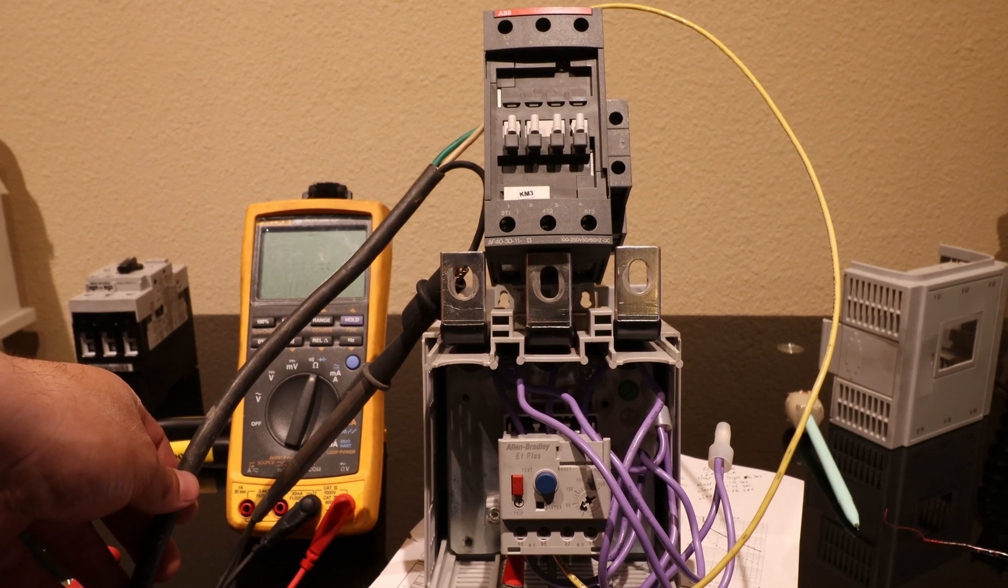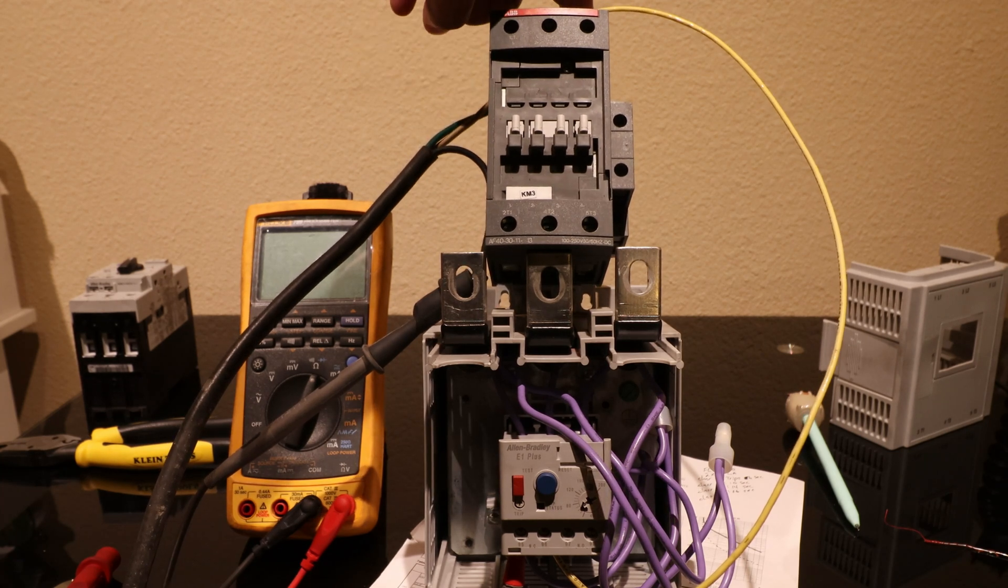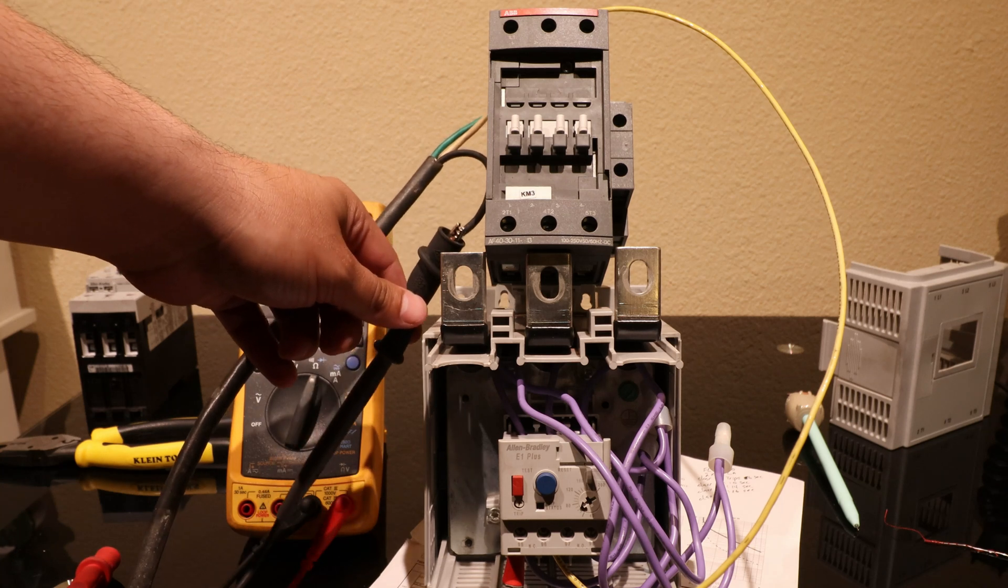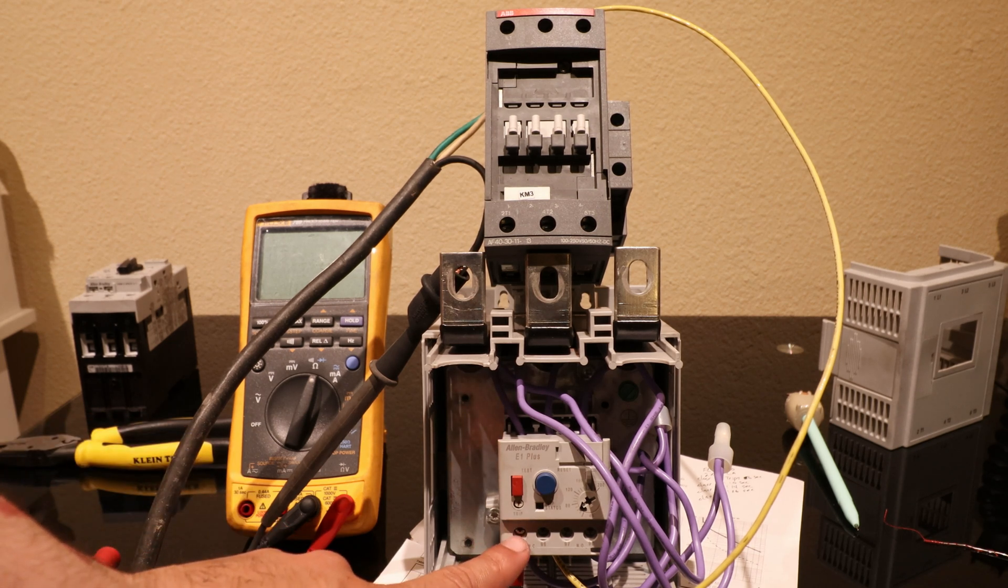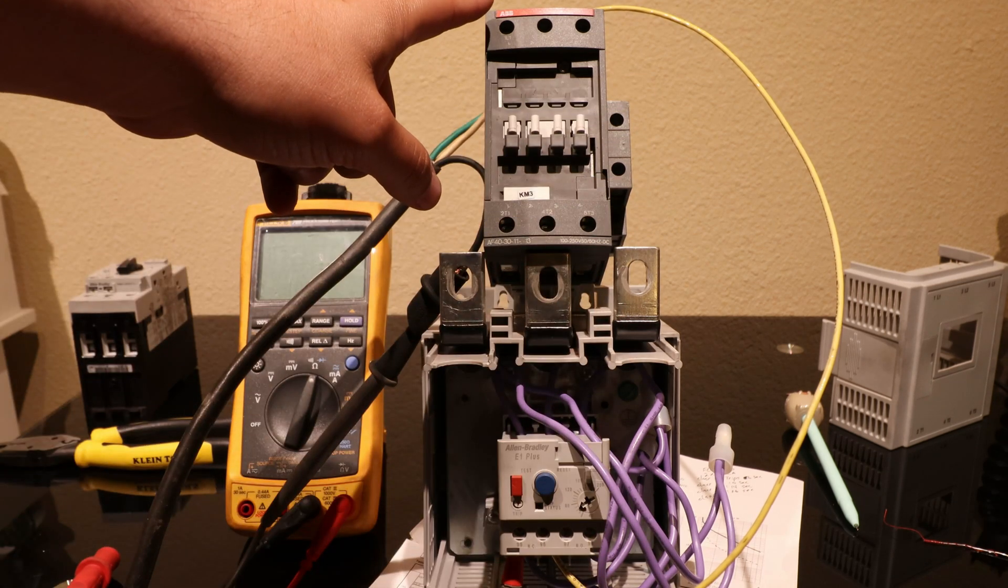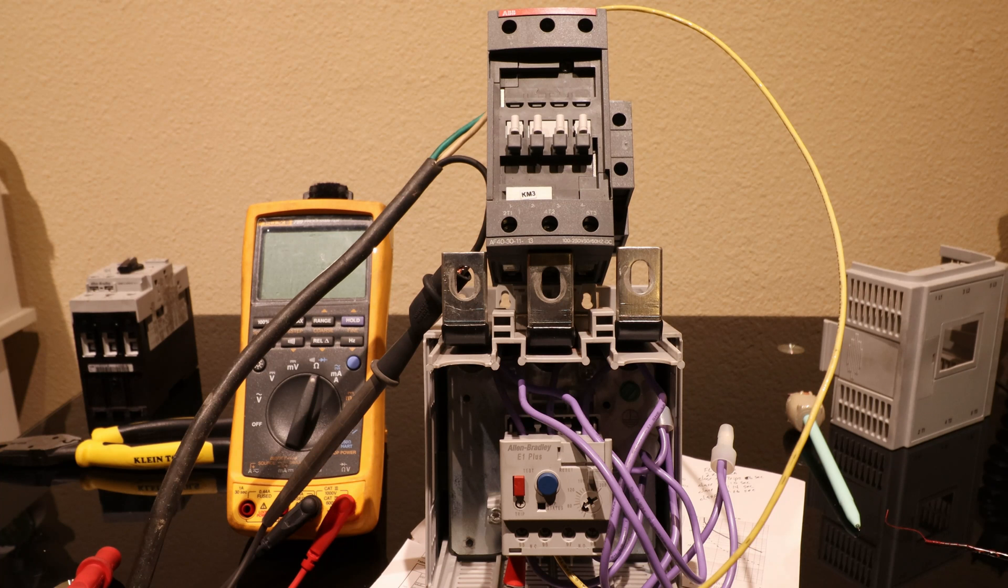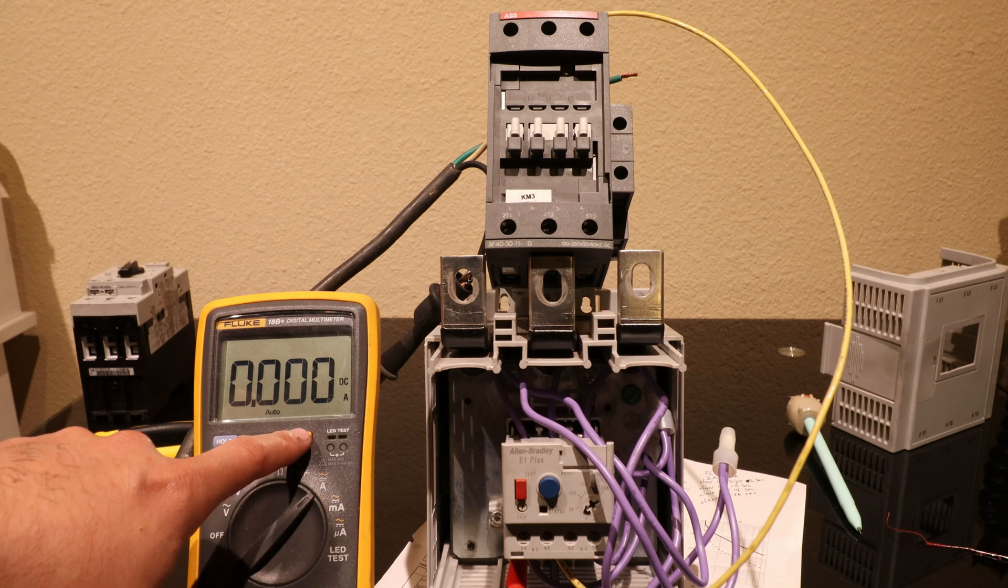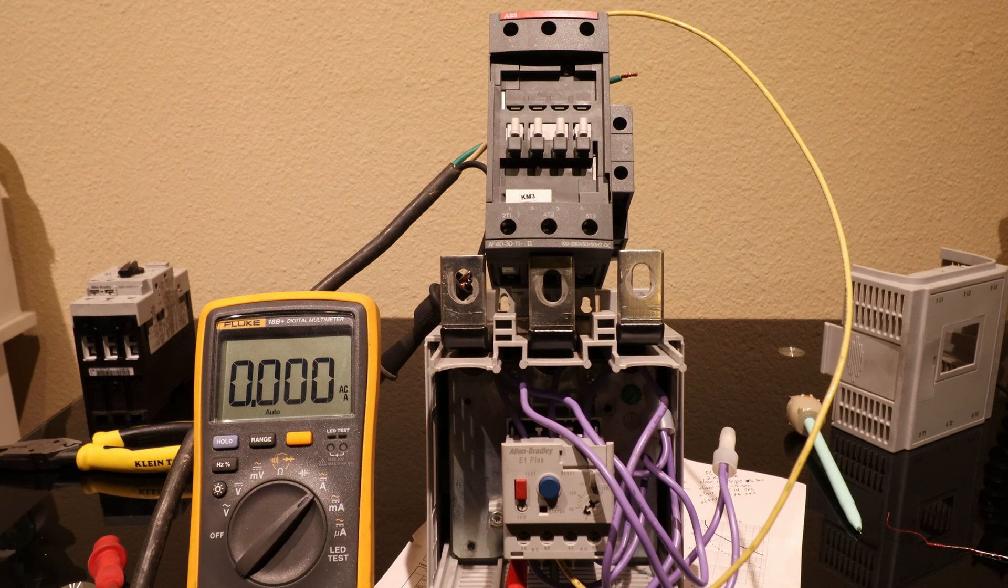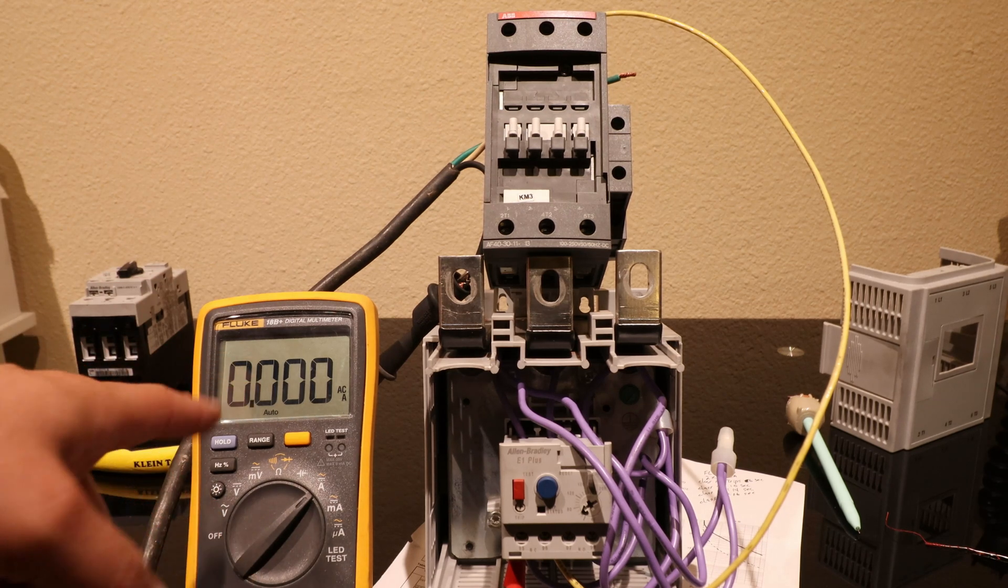All right so let's see how we got this guy wired. We got my safety cord, white wire is for the neutral on the right side of the contact right here to pull in solenoid. Black wire, for funsies, I got it running over here through my meter, through my meter out the red into this normally closed contact and out the other normally closed contact in a yellow wire to feed the hot to the other side of this solenoid. I got the meter wired in series so I can see how many amps the solenoid and the contactor is drawing amperage. Yellow for AC. All right now we're going to plug in our safety cord, you're going to watch the contactor pull in and an amperage show on the doodad.